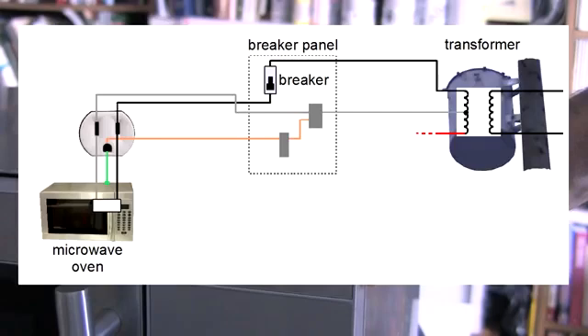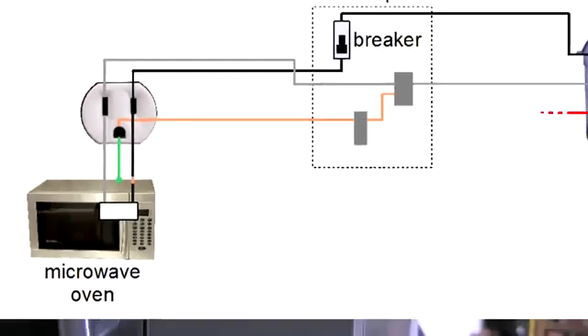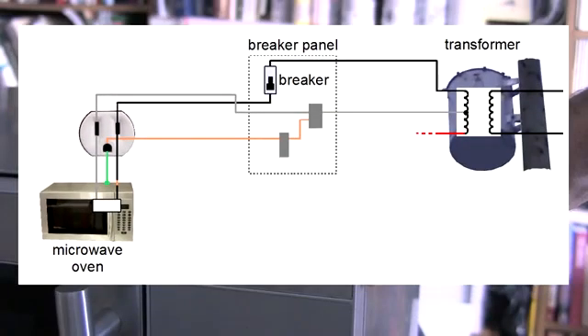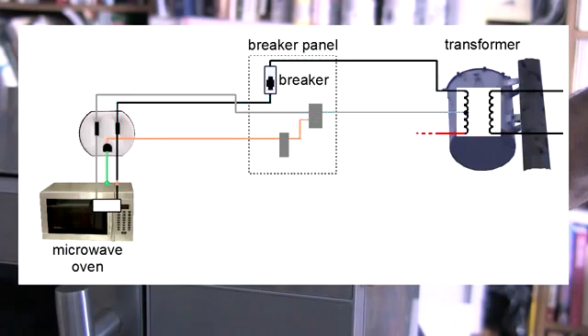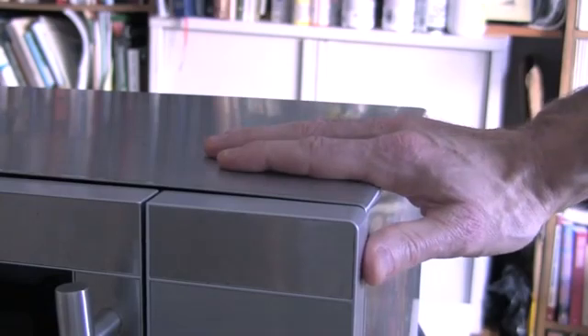Let's look at it again on the diagram. The problem starts when the insulation on the hot wire breaks and the wire touches the microwave oven's case. Since the case is connected to the ground wire, we now have this complete circuit along the ground wire to the breaker panel, then along the neutral wire, onward to the transformer on the pole, through the transformer's coil, back through the hot, through the breaker, and continuing to the hot in the microwave oven where it's touching the case. There's very little resistance along that circuit, and so the electrical current will be very high — high enough to trip the breaker, which opens the circuit, making it safe to touch the microwave oven's case again.